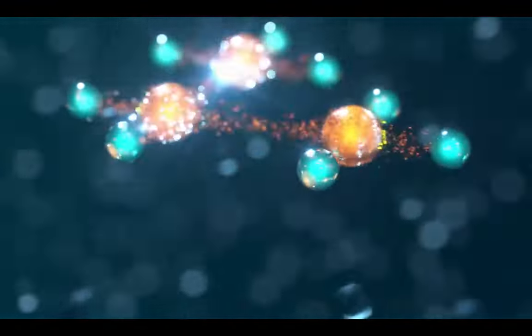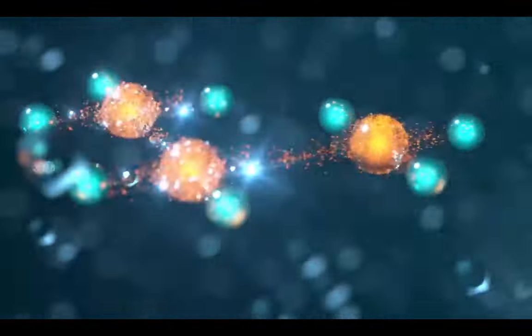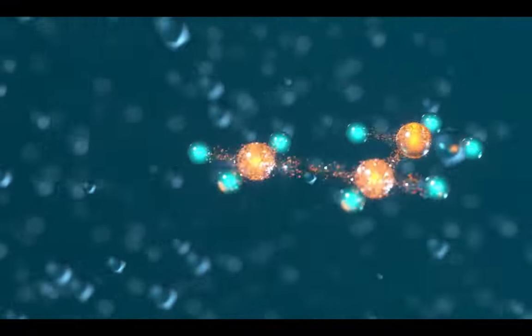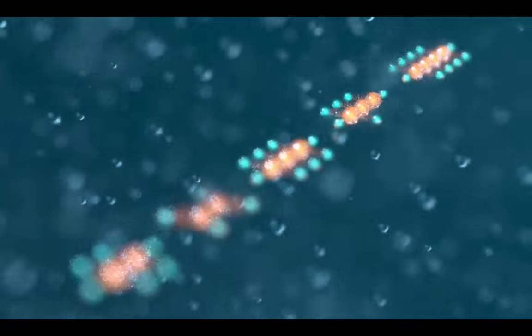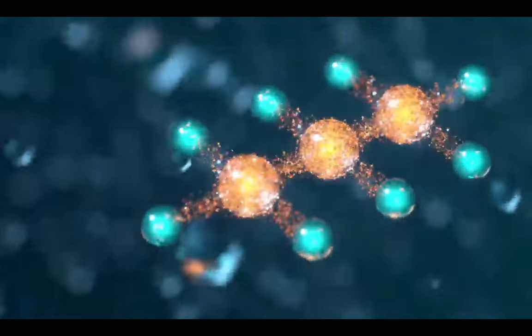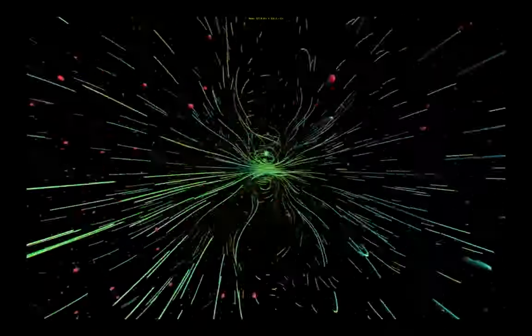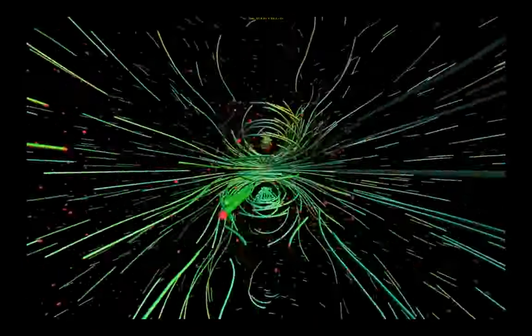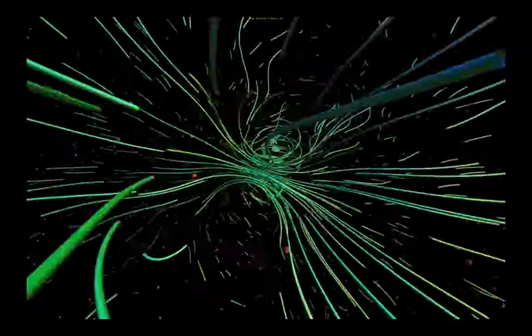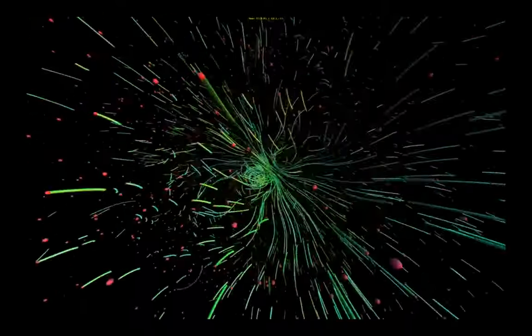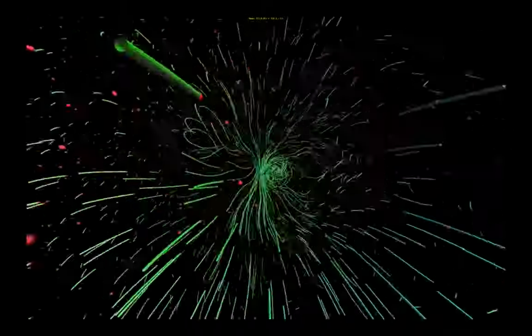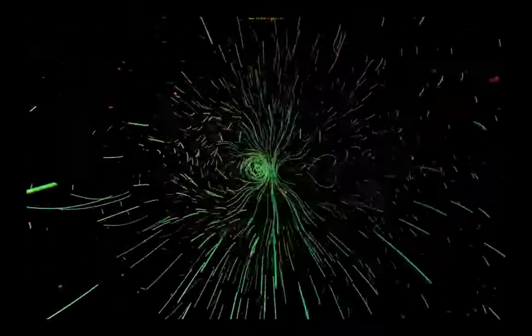This intense bombardment results in many fragments of charged and neutral molecules. Now normally, these bits and pieces of molecules are not stable beyond a few microseconds and will recombine quickly.